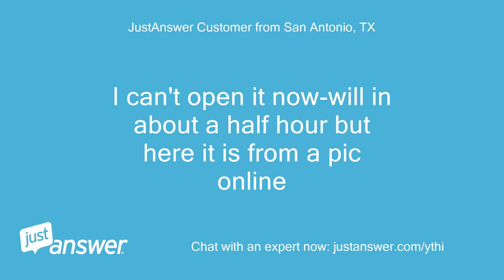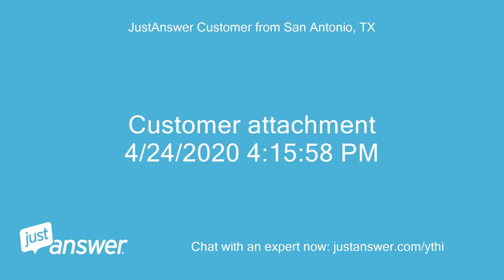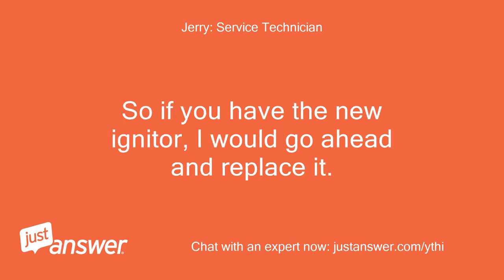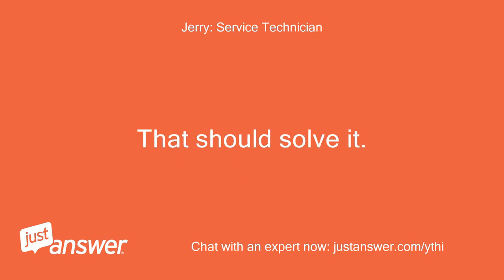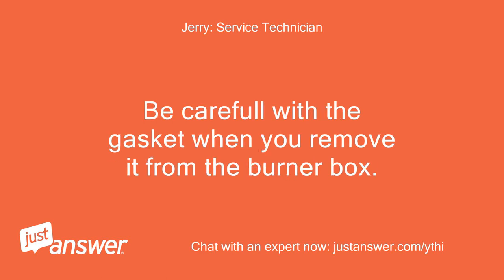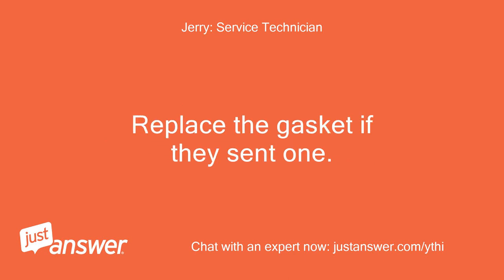I can't open it now — well, in about a half hour — but here is a pic from online. [Customer attachment: April 24, 2020.] Okay, yes, I believe this unit has the igniter and sensor in one. So if you have the new igniter, I would go ahead and replace it — that should solve it. It is located inside the burner box and has two thick wires attached to it. Be careful with the gasket when you remove it from the burner box, and replace the gasket if they sent one.